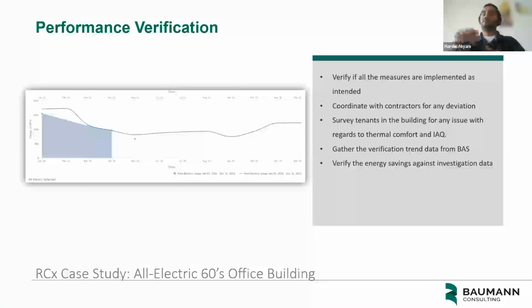Next, once all the measures were implemented by the contractors, we went into the verification phase. It is very important to verify the measure persistence, not only whether they are implemented properly, but whether they are staying implemented for a longer time. That is where you will be able to see the energy savings over a longer period of time. During this verification phase, we coordinated with the controls contractor and the mechanical contractor, always ensuring whether the measures are implemented as they were intended or not.